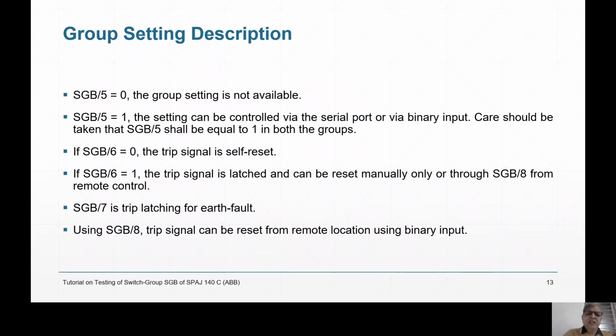SGB 6 is for latching the trip signal. If you see what happens, a fault occurs. So the relay senses the fault, then the relay operates. Relay operates means the breaker trips. Breaker trips means the current through the relay is zero. So the relay will reset automatically. Most of the relays are self-reset. But if you do not want the relay to be self-reset and you want to hand reset it, then you can do it using SGB 6.